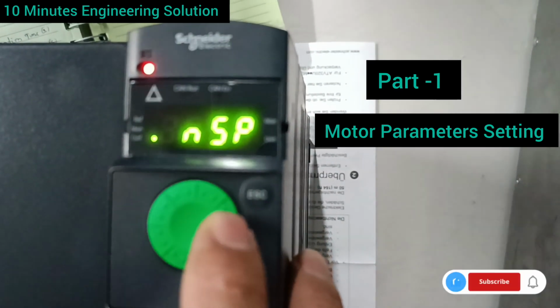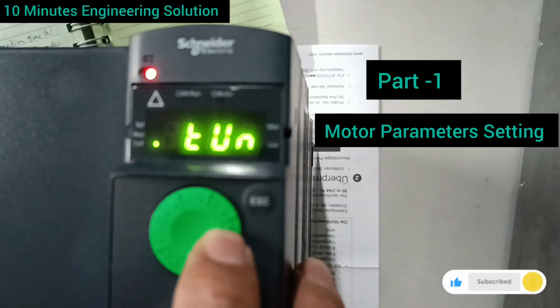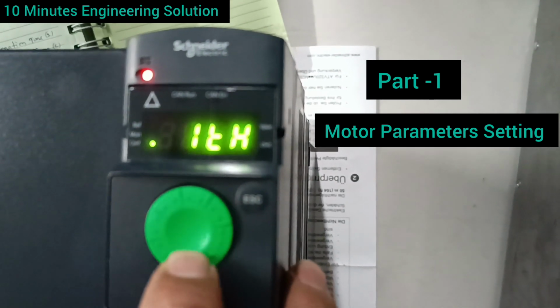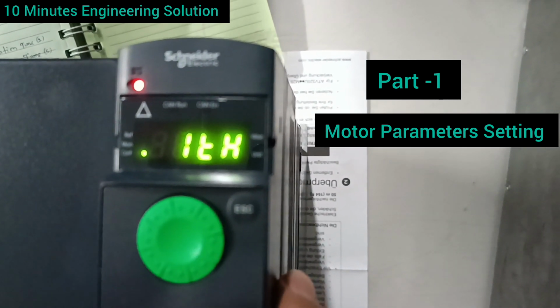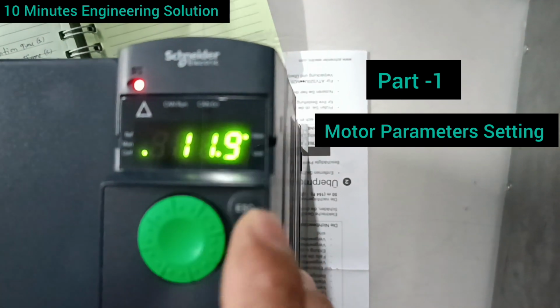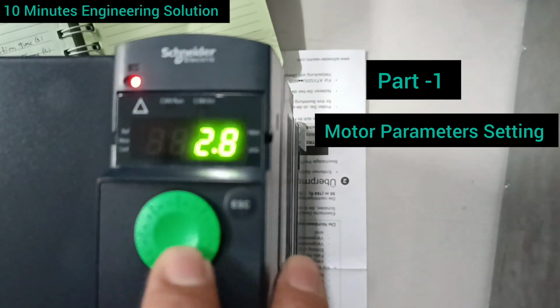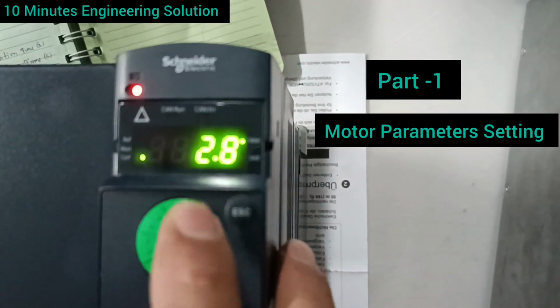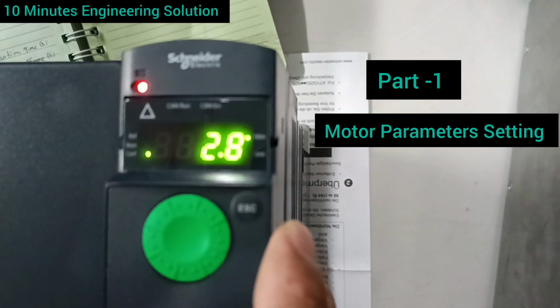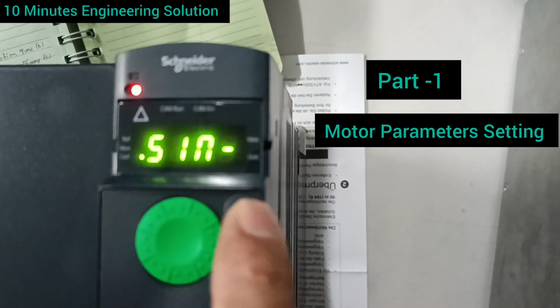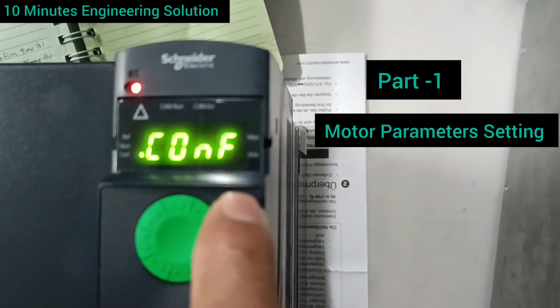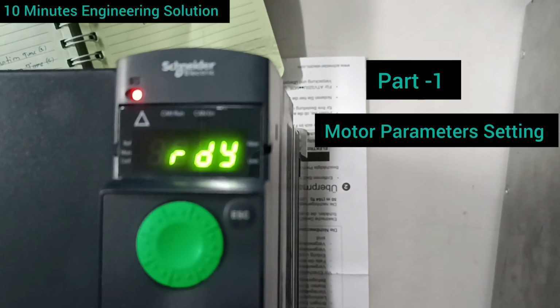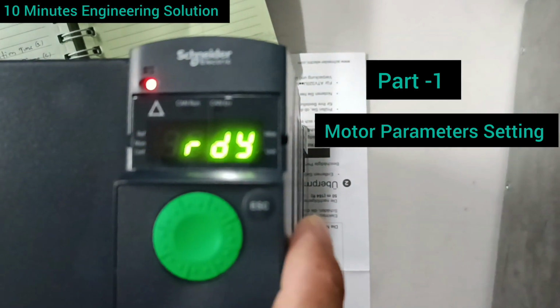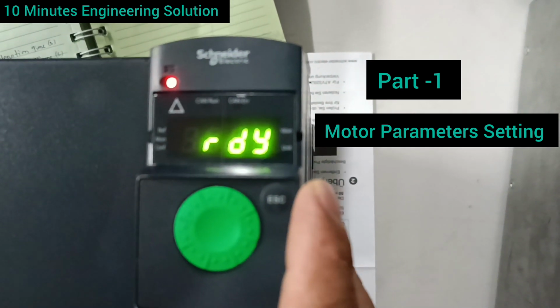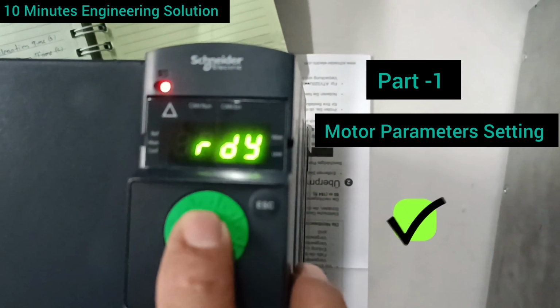Okay, and then I have to set the ITH, the motor thermal current. This is the motor thermal protection current. This is the standard 2.8. So I just set all the values. This is the motor parameter settings I have done completely. The configuration parameter part 1 is done. You can see the right side of the screen.